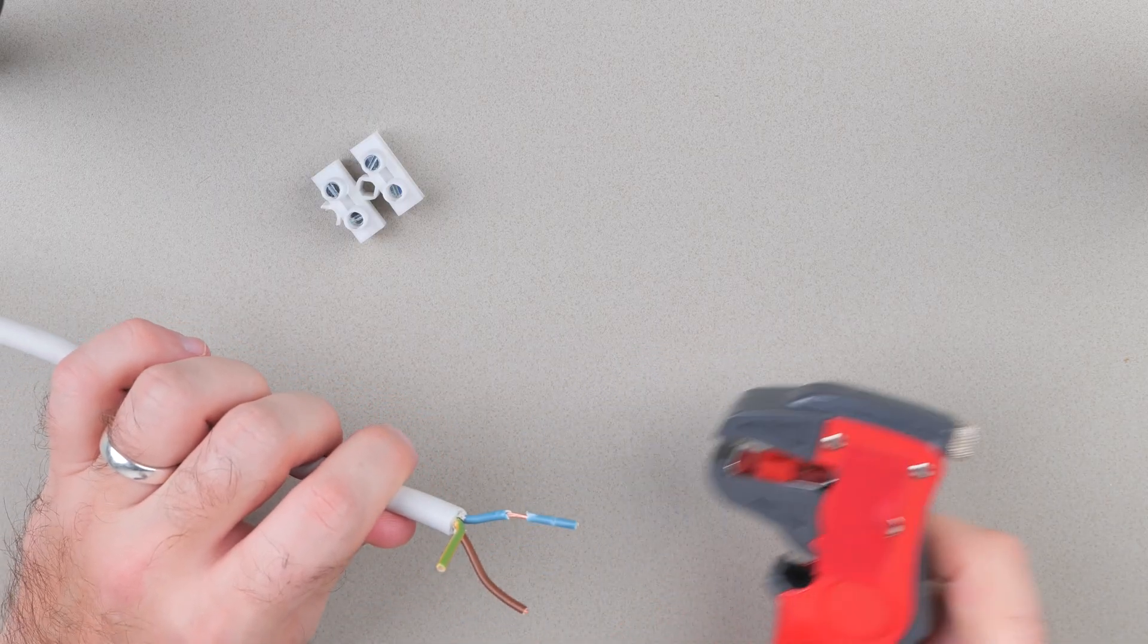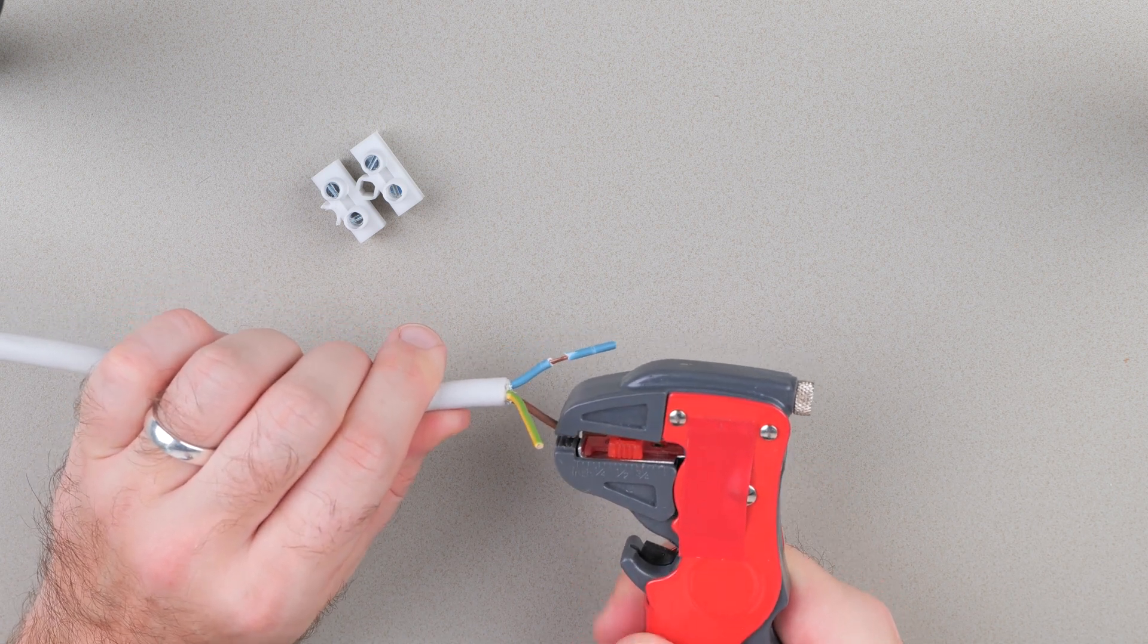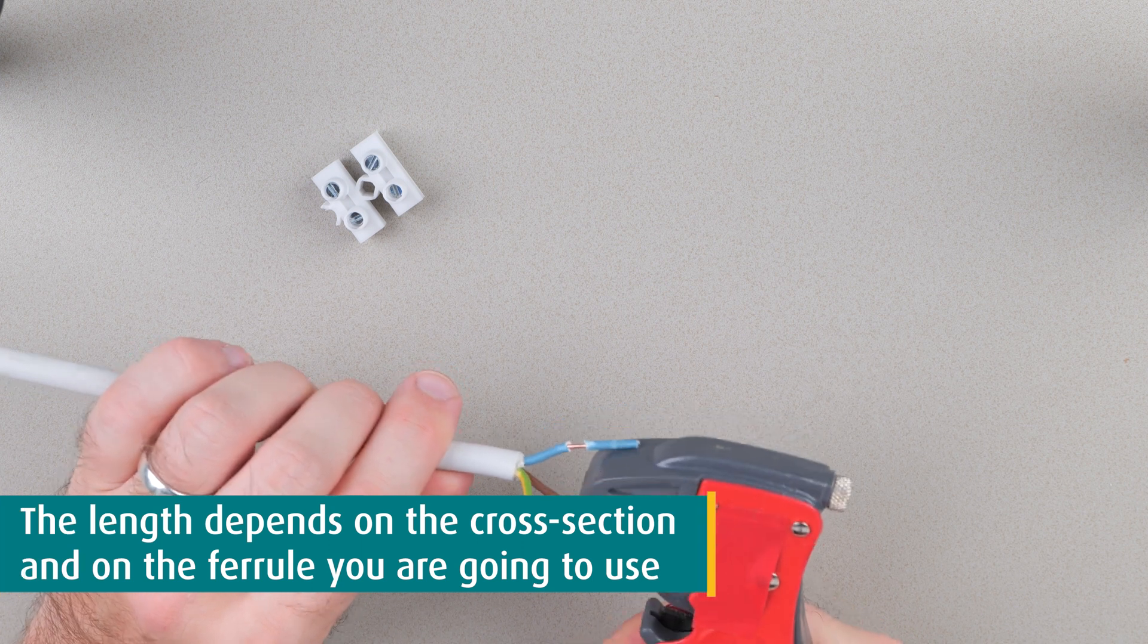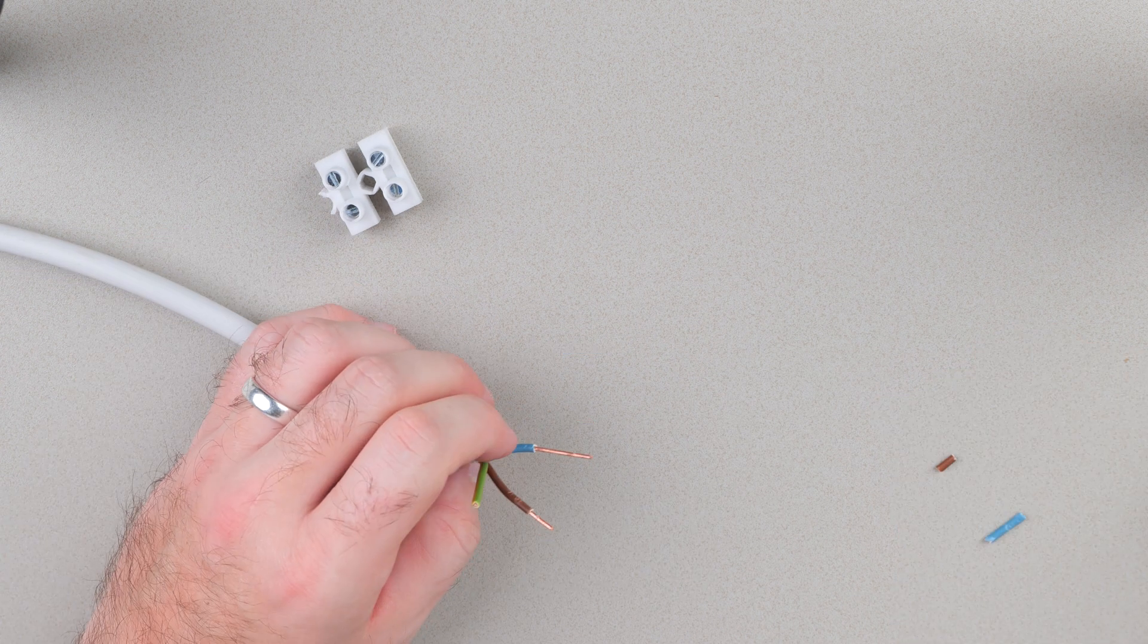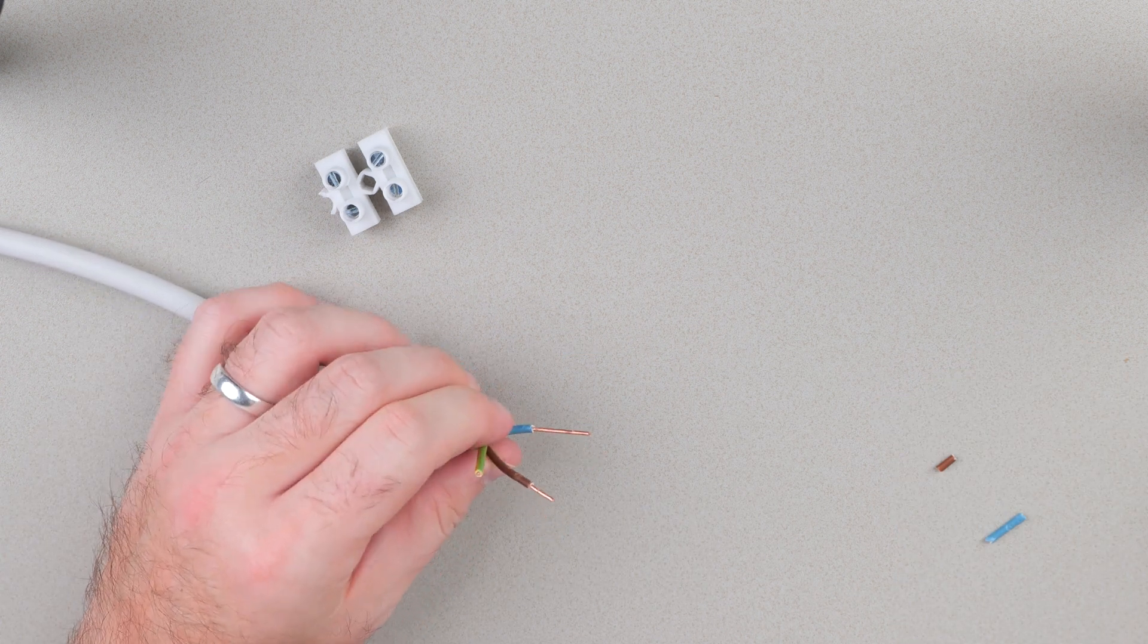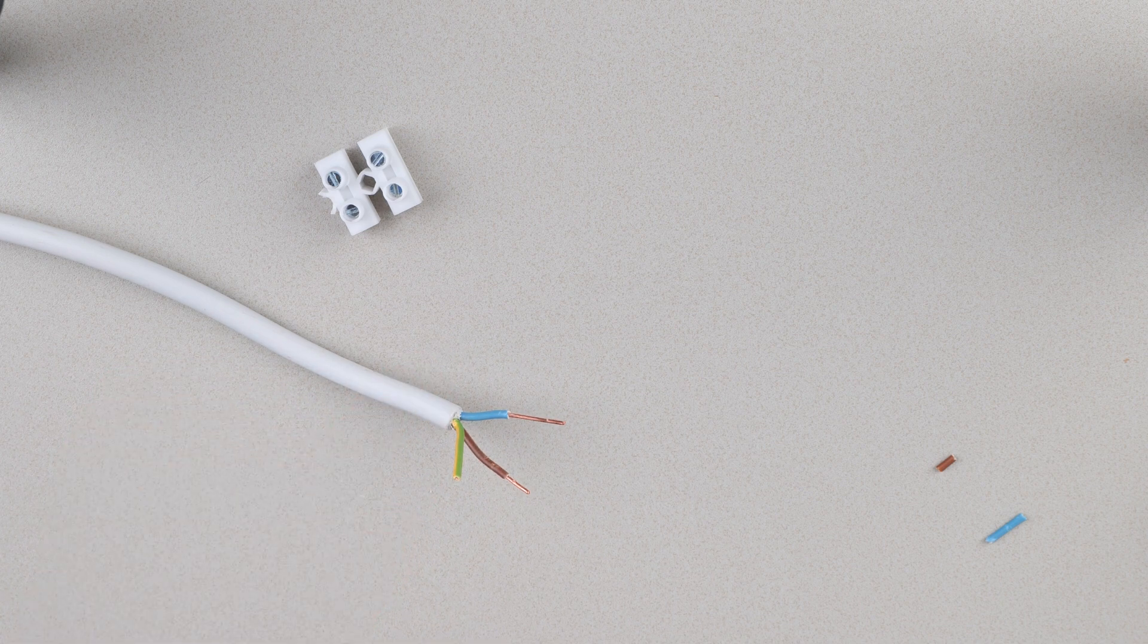The length of the uninsulated part depends on the cross section and the according ferrule you are going to use. I will uninsulate a part of roughly 8mm length. A wire stripper is much faster and more comfortable than a knife, so it's highly recommended to use one.